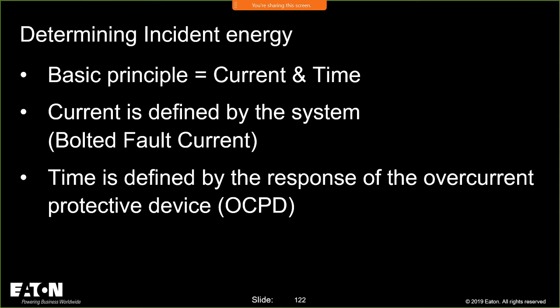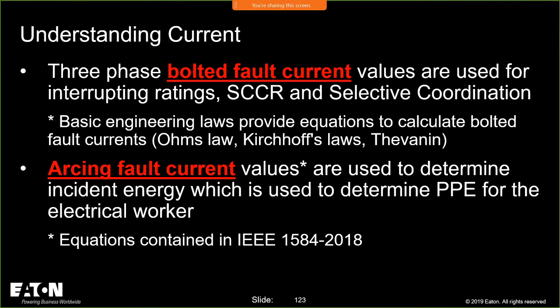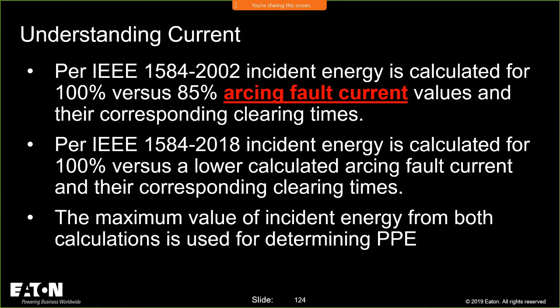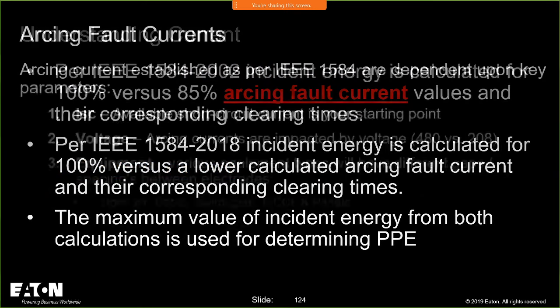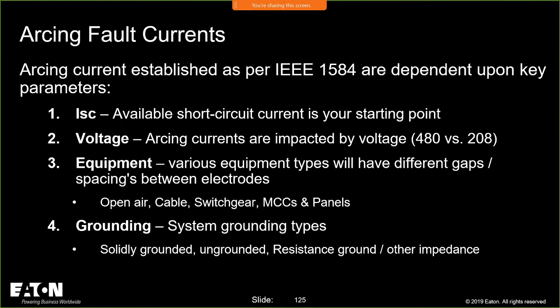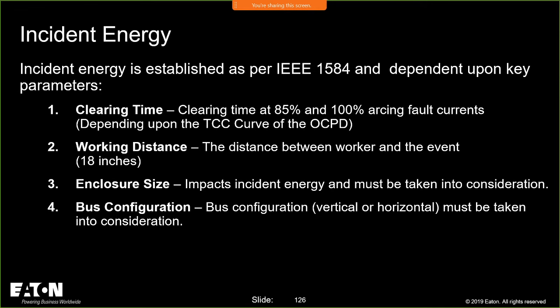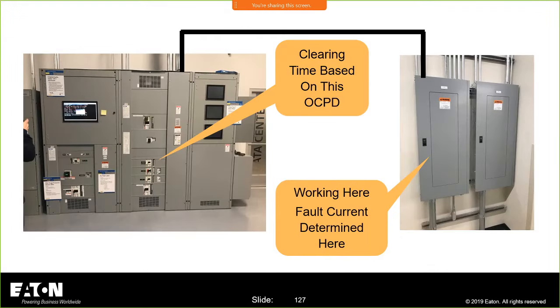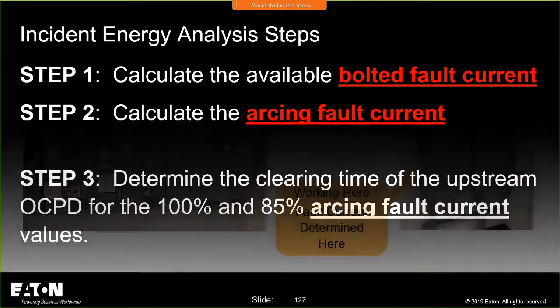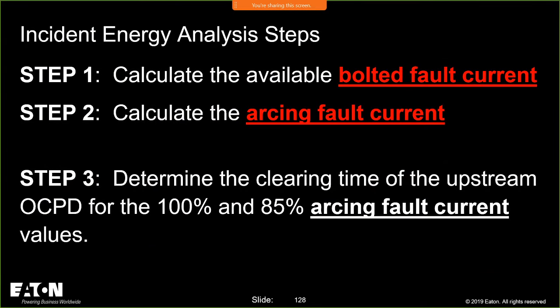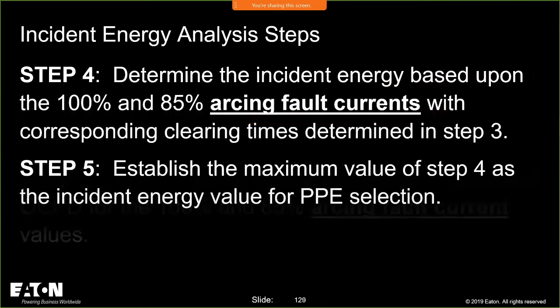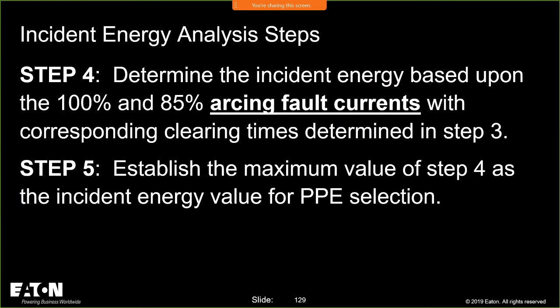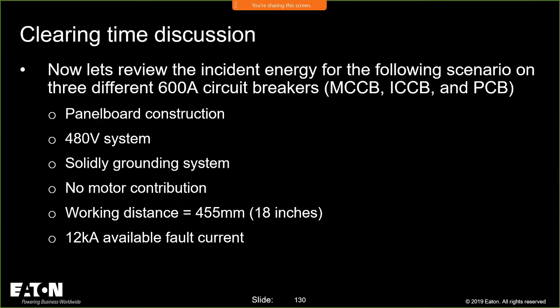And I talked about this already. I believe it was last week, but we have to know the bolted fault current. We have to know the arcing fault current, and based upon the clearing times, determine the amount of energy, and that's going to be dependent upon the overcurrent protective device that you're downstream of. So I'm just walking through the process of an incident energy analysis. It's determine the bolted fault current, establish the arcing current and the clearing times, and calculate the incident energy. Those are basically your 3 steps to determining. Actually, there's about 5 steps to determine the incident energy. And you pick the longest clearing time, which could get you a higher incident energy, which could be a lower fault current.